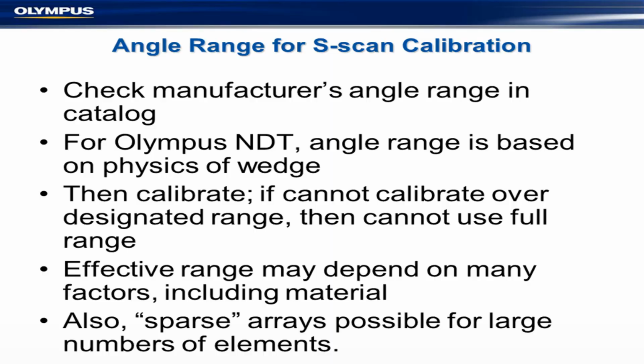Okay, so how far can you scan with your angles if we're doing a sectorial scan? Well, first thing you do is you look at the manufacturer's angle range in the catalogue. In our case, it's based on physics, so when the beam is bumping into the end of the wedge, then that's it. You cannot go any further than that, otherwise you lose half your beam. That's a kind of no-brainer, if you like.